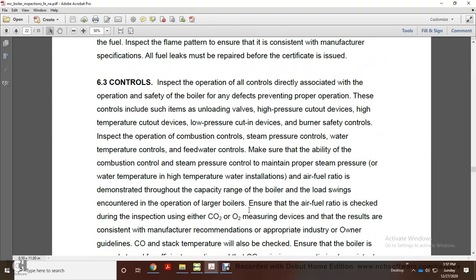Alright, 6.3 Controls. Inspect the operation of all of the controls associated with the operating safety of the boiler that affect proper operation. These controls include such items as unloading valves, high pressure cutout devices, high temperature cutout devices, low pressure cut-in devices, burner safety controls, combustion controls, steam pressure control, water temperature control, and feed water controls. Make sure the combustion control and steam pressure control maintain the proper steam pressure or water temperature, and in high temperature water, the fuel and airflow ratio demonstrated across the capacity range of the boiler.